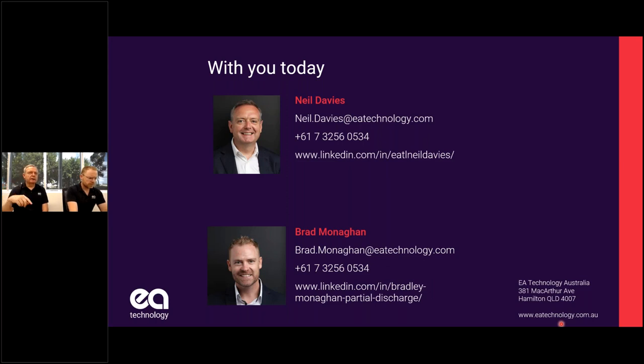So what you'll find is anyone who's in a temperate climate, where you've got the spring and the autumn and the big cycling, like Brisbane at this time of year, where you get quite cool nights and warmer in the daytime, you get that cycling through the dew point, and that's the sort of time where discharge comes and goes. So sometimes the time that you're taking the test can be very important.